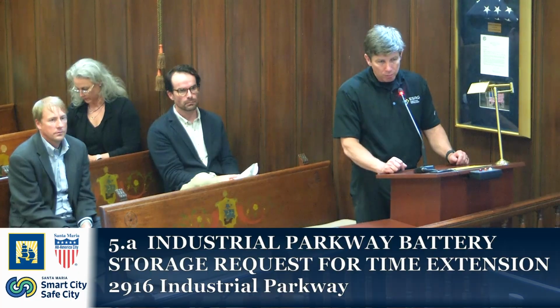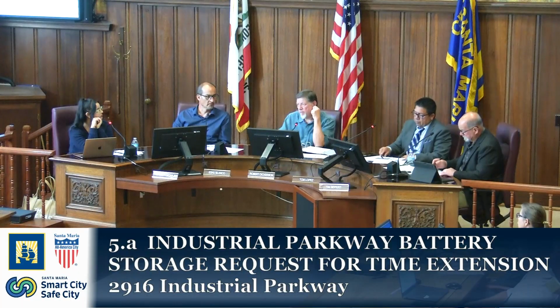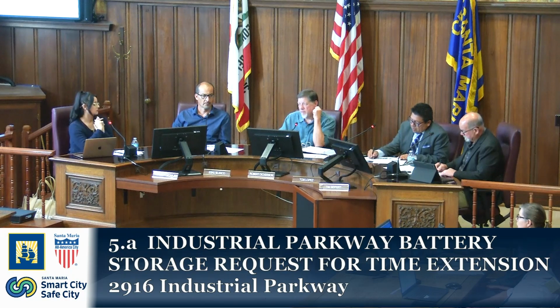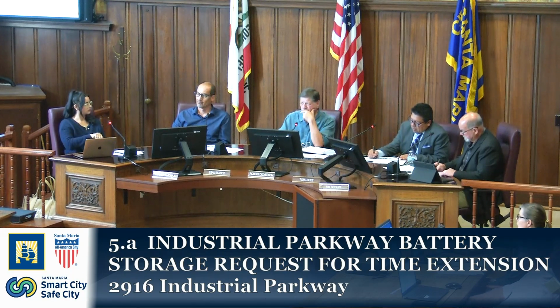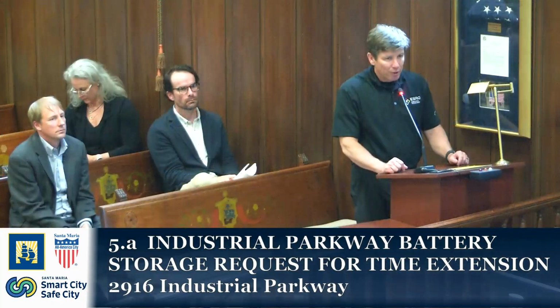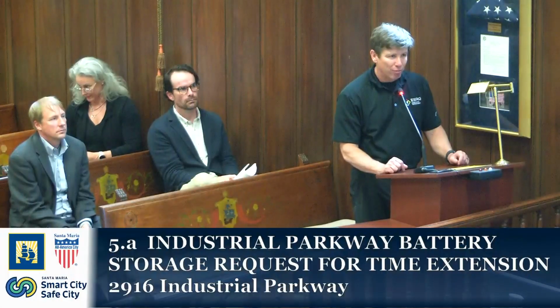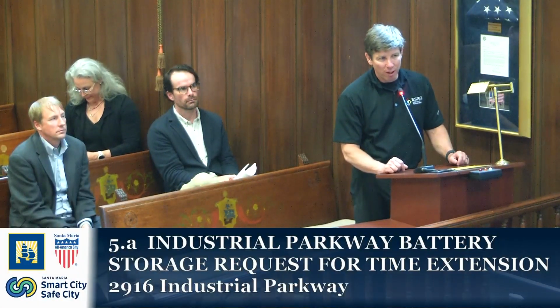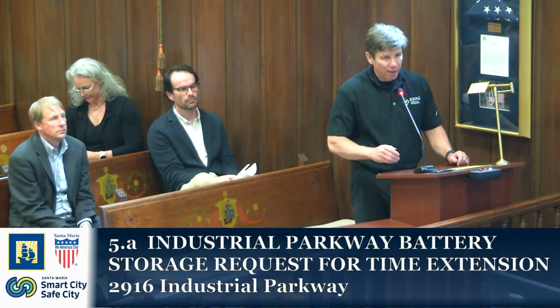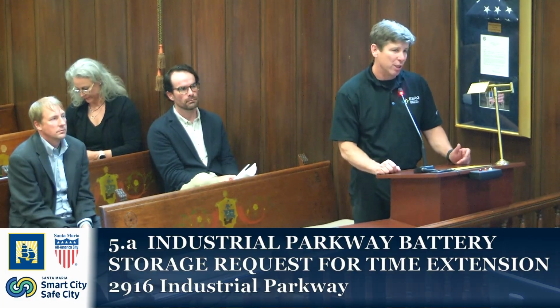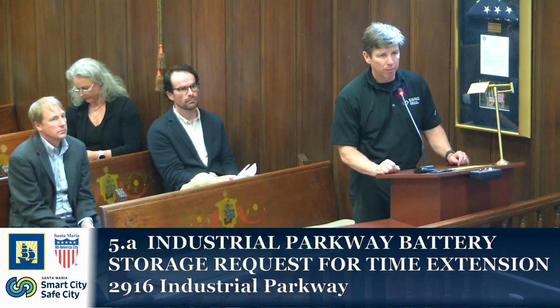So you want the firefighters back 100 feet, but you said it's basically safe having 12 feet between these units. In theory, then, isn't it 12 feet for a firefighter also? No — I wouldn't want a firefighter even entering the fenced area, mostly because of the electrical hazard.